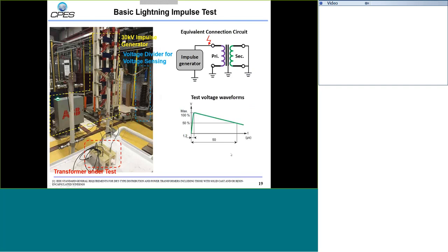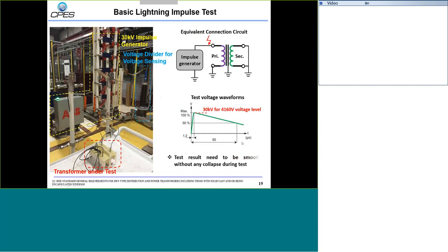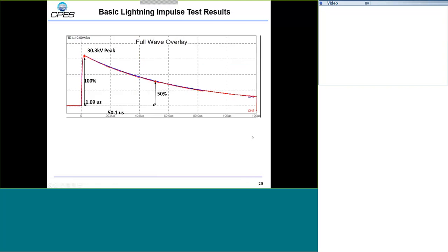The next step was insulation testing, done in collaboration with ABB. The first test was a lightning impulse test: we applied 30 kV to this transformer for 50 microseconds and measured whether the voltage curve is smooth or shows any collapse. A smooth curve means we pass the test. The testing results show that for both test repetitions, the curve is very smooth — the highest voltage reaches 30.3 kV and gradually reduces. The two curves overlap very well, confirming we passed this impulse test in both runs.